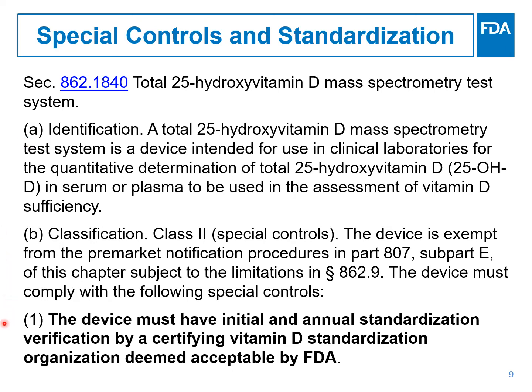This, in combination with special control number 1, which requires initial and annual standardization verification by a certifying vitamin D standardization organization, allowed FDA to exempt the device from the pre-market notification procedures, even though it is a Class II device. This is to say that FDA thinks that standardization usually helps. And we have leveraged data from standardization programs to inform our regulatory decisions. And the bottom line message is that as a regulatory agency, we don't want to be a barrier or be perceived as a barrier to achieving standardization.